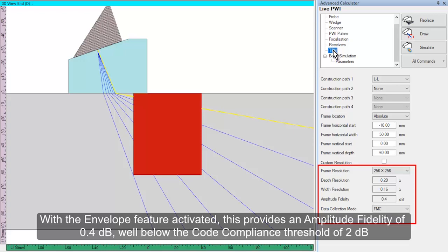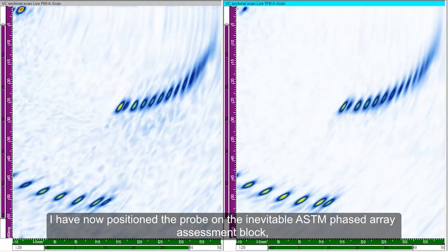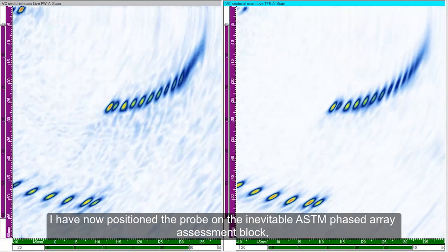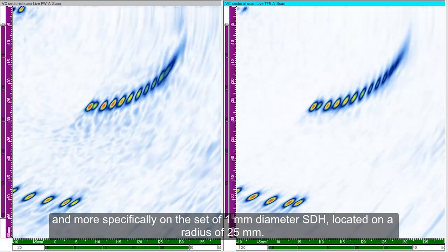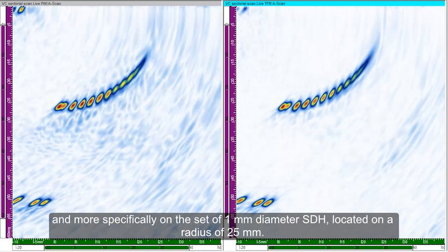I have now positioned the probe on the inevitable ASTM phased array assessment block, and more specifically on the set of 1 mm diameter side drilled holes located on a radius of 25 mm.